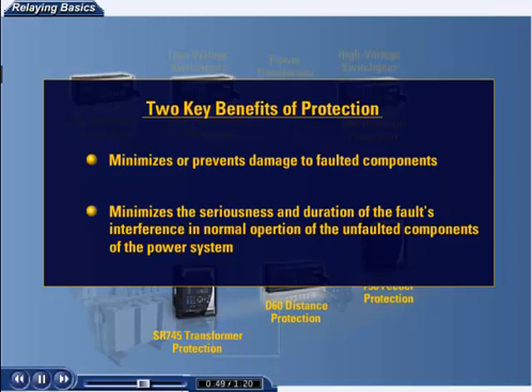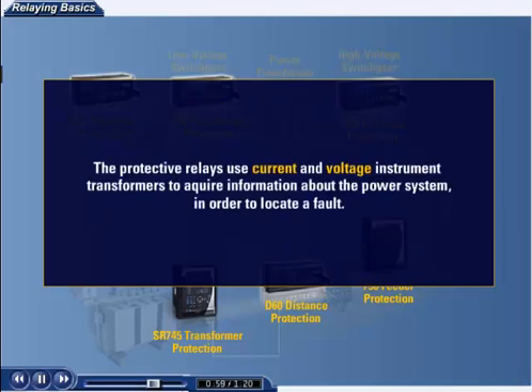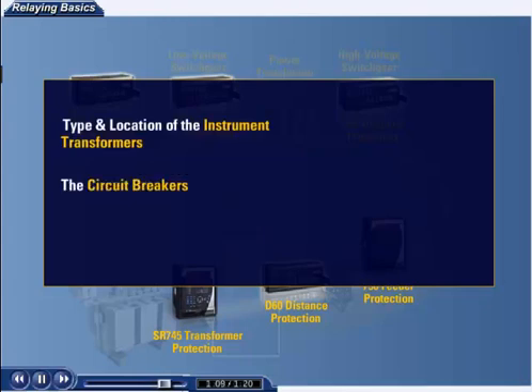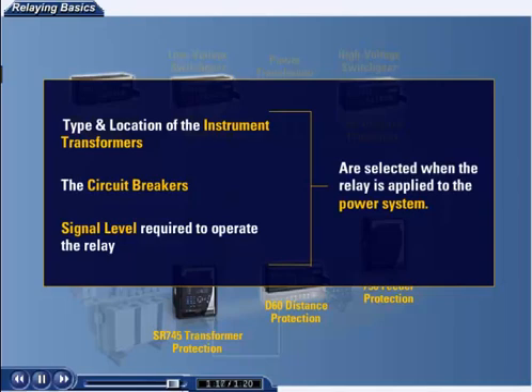In many cases, the unfaulted parts of the power system can supply the additional power to replace what was normally supplied through the faulted component. The protective relay uses current and voltage instrument transformers to acquire information about the system, such that a fault can be located. The type and location of the instrument transformers, the circuit breaker which is to be tripped by the protective relay when it operates, and the signal level required to operate the relay is selected when the relay is applied to the power system.